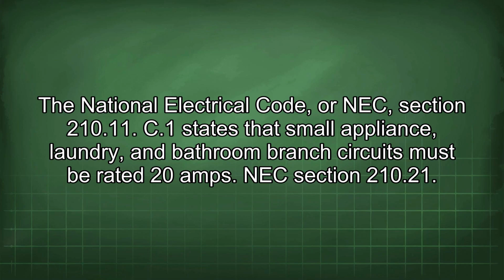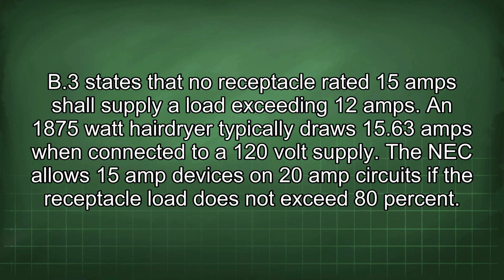The National Electrical Code, or NEC, Section 210.11(C)(1) states that small appliance, laundry, and bathroom branch circuits must be rated 20 amps. NEC Section 210.21(B)(3) states that no receptacle rated 15 amps shall supply a load exceeding 12 amps. An 1875-watt hairdryer typically draws 15.63 amps when connected to a 120-volt supply.